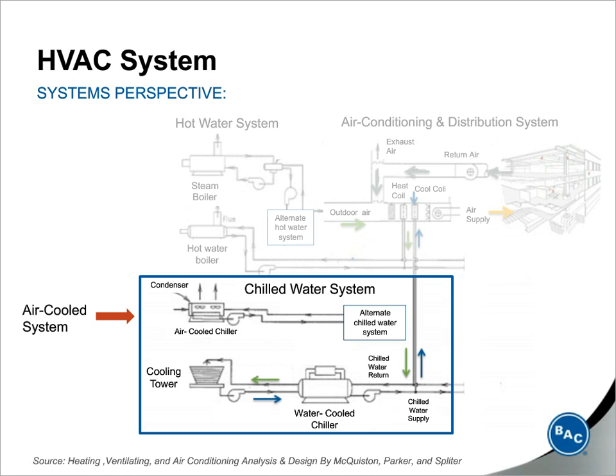This heat is typically rejected through sensible cooling and it depends on the outdoor ambient dry bulb temperature, and this is very important, that it cools to the dry bulb temperature. Now, water-cooled systems, on the other hand, have a condenser water loop that includes a water-cooled chiller and a condenser pump, and then heat is rejected from the cooling tower through evaporative cooling, which depends on the outdoor ambient wet bulb temperature instead of the dry bulb temperature.